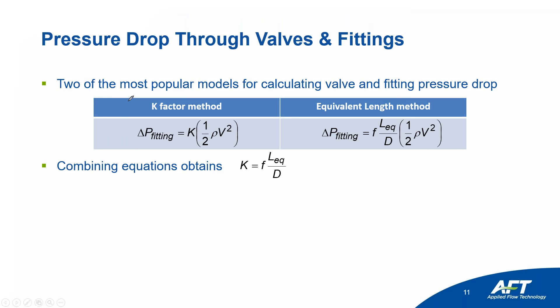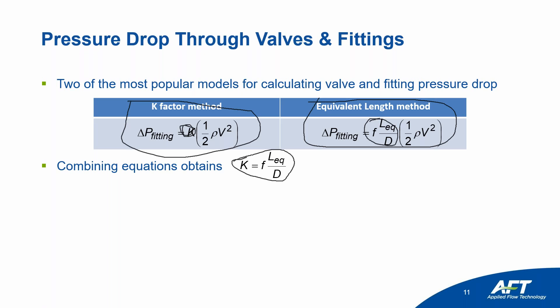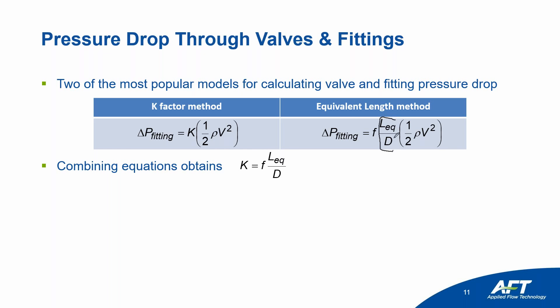The K-factor method sets pressure loss across a fitting equal to K times one-half rho V-squared. It's the more common method with lots of data available, and many K-factor loss models are built into Fathom. The equivalent length method uses an FL/D term to characterize pressure loss across fittings. Combining the two equations shows how K-factors and equivalent lengths relate to each other. A feature introduced in Fathom 9 lets you model equivalent lengths directly when you have them for your fittings.